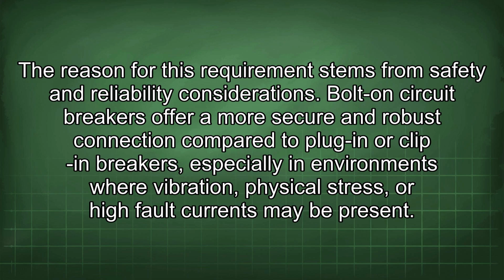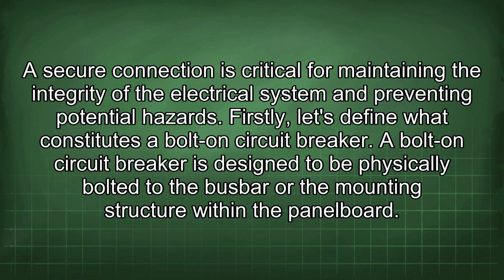The reason for this requirement stems from safety and reliability considerations. Bolt-on circuit breakers offer a more secure and robust connection compared to plug-in or clip-in breakers, especially in environments where vibration, physical stress, or high fault currents may be present. A secure connection is critical for maintaining the integrity of the electrical system and preventing potential hazards.